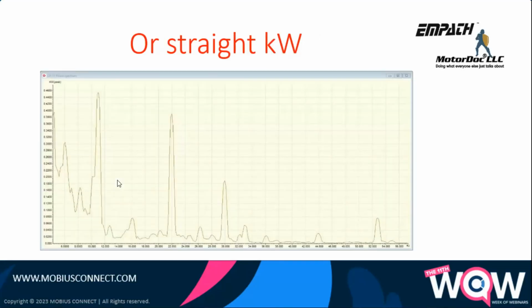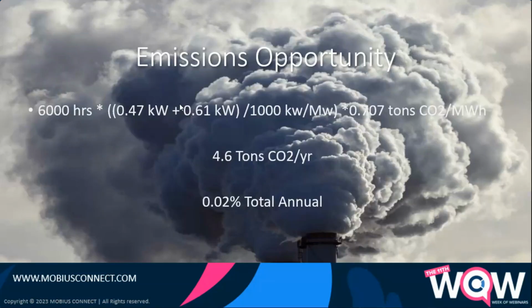Or I can go in our particular ESA device, we actually calculate everything out. There's the values right there. I just look at the peaks. The newest version of our system actually puts the lines up on it and takes the measurements for you, but that's neither here nor there. You can take a look at straight kilowatts. Now, if you don't have this and you just have a power meter, use the power meter before and after. Your biggest opportunities, including things like bearing wear and bearing greasing, that's a big one. Things like that are all going to be measurable values before and after, as long as you keep the load the same. So the emission opportunity for that one, 0.707, yeah, there it is, 4.6 tons of CO2 per year, closer to 5, sorry. Math in my head, not a good thing.